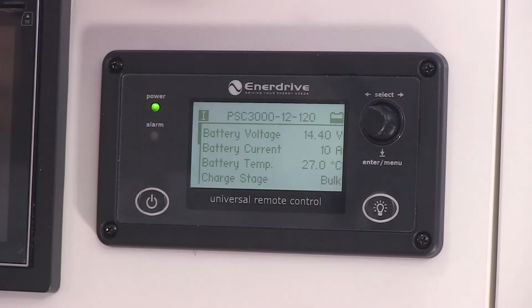I mentioned earlier on that one of the key features of the Combi is its ability to support a load. A fine example would be such as a generator. When you plug in a generator, let's presume it's a 2 kVA generator, and typically that would be good for approximately 7 amps AC. I appreciate not everyone is so technically minded that they understand the maths of what equates to what, but I assure you in this case at 2 kVA we would lean towards 7 amps AC.